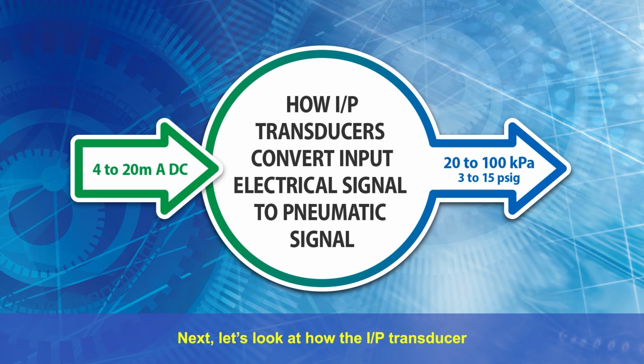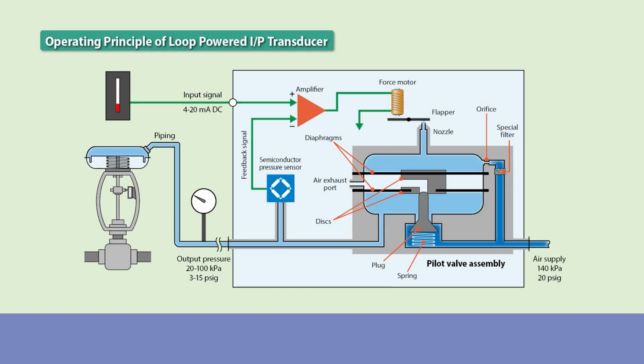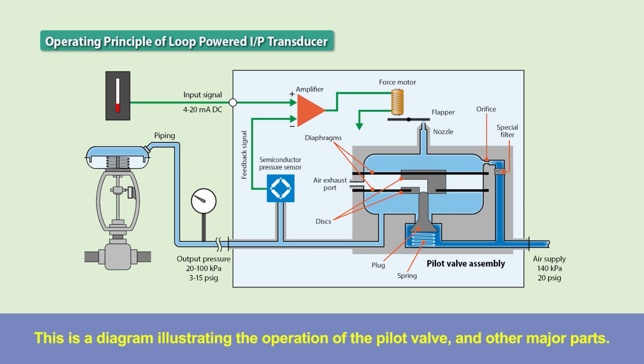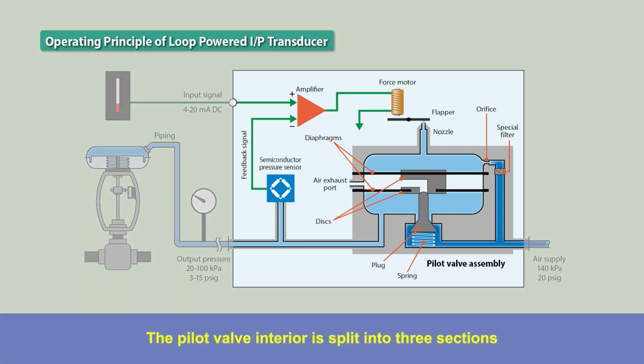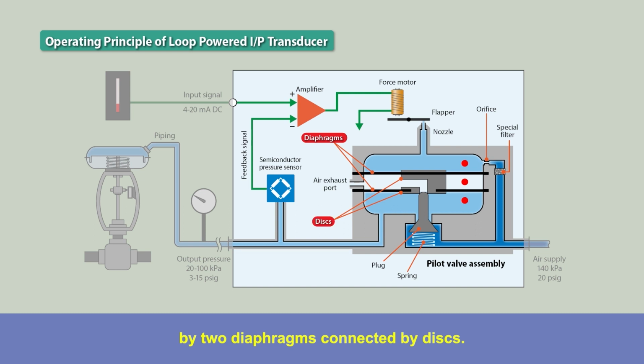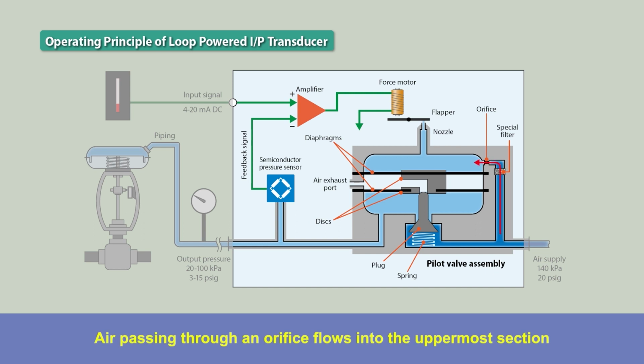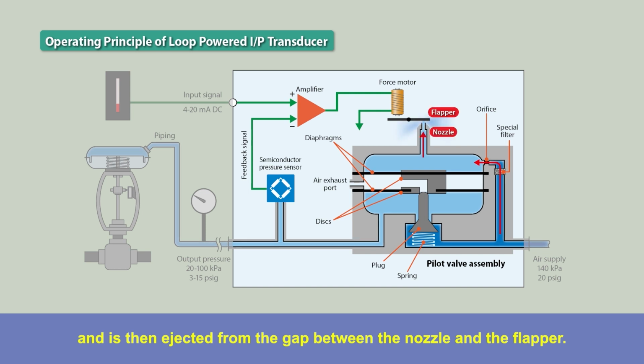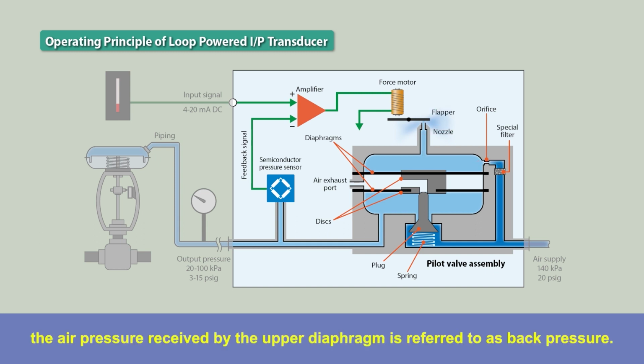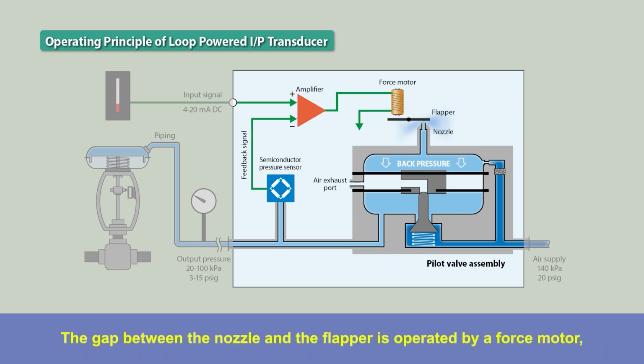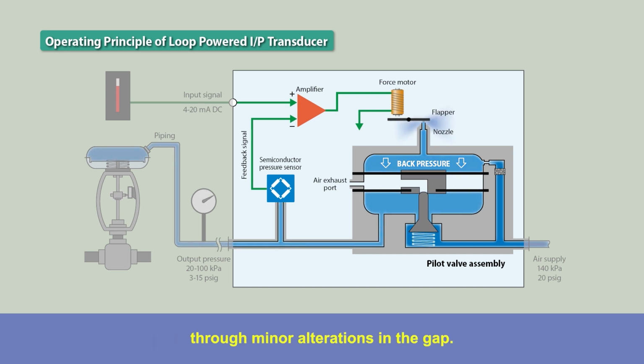Next, let's look at how the I-to-P transducer converts the input electrical signal to a pneumatic signal. This is a diagram illustrating the operation of the pilot valve and other major parts. The pilot valve interior is split into 3 sections by 2 diaphragms connected by discs. Air passing through an orifice flows into the uppermost section and is then ejected from the gap between the nozzle and the flapper. When doing so, the air pressure received by the upper diaphragm is referred to as back pressure. The gap between the nozzle and the flapper is operated by a force motor, which can greatly change the amount of back pressure through minor alterations in the gap.